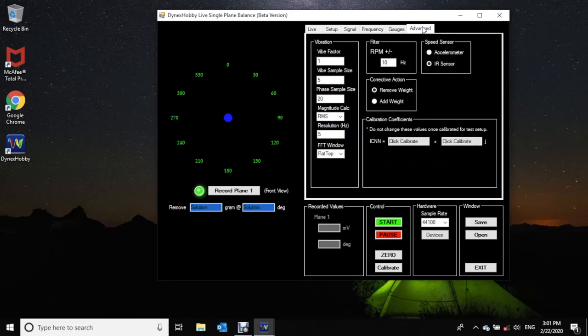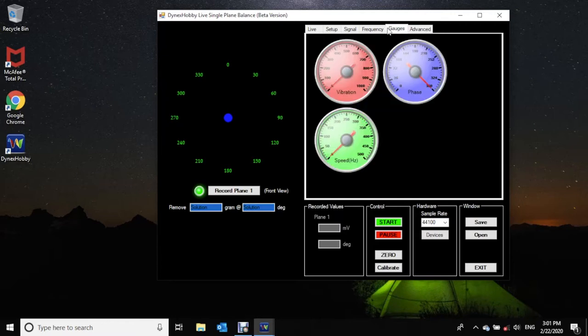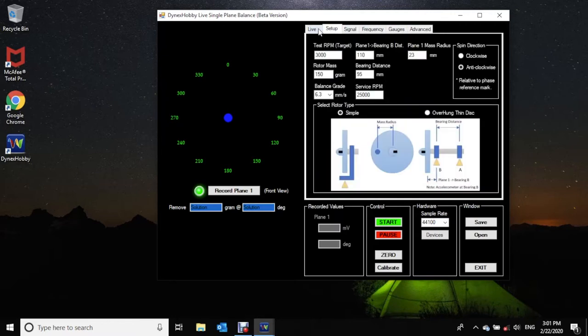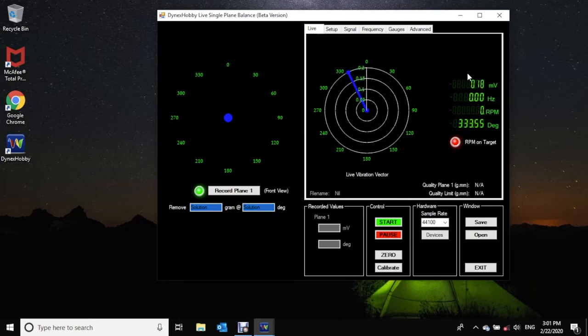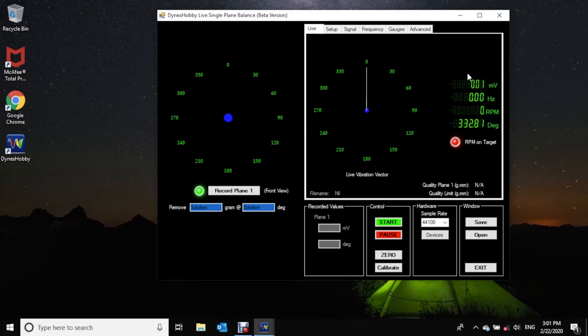In the advanced setup, a lot of these parameters can be left as they are by default. The only thing you really need to change here is how you want to correct the imbalance. In this case, I tend to use add weight rather than remove, because it's easier to add the weight and see what effect it has before you go and actually modify the EDF. So those are the main parameters that we need to set. I'll just go back to the main live window.